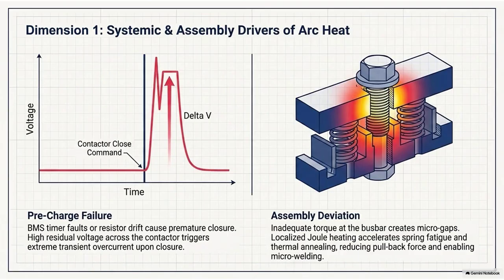Electricity, specifically high amperage direct current, requires a massive surface area to flow smoothly. When you constrict that flow through a reduced contact patch, you dramatically increase the contact impedance at that specific joint. Impedance is essentially electrical resistance. And the fundamental law of electronics is that where there is electrical resistance, there's friction, and electrical friction generates heat. Right. We refer to it as localized Joule heating, which is governed by the equation current squared times resistance. The math just doesn't care.